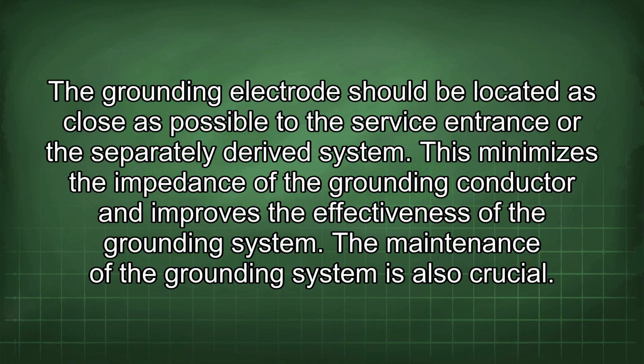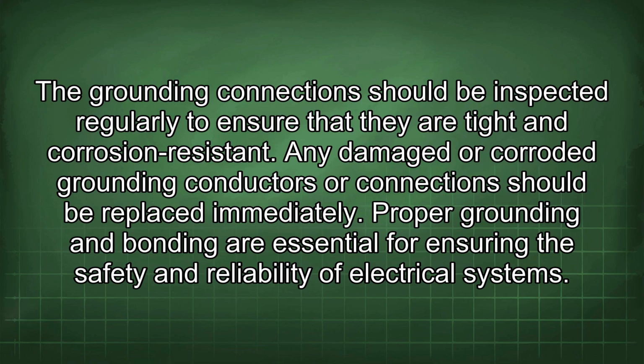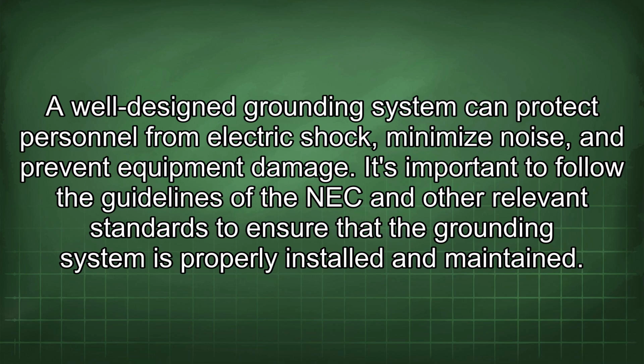The maintenance of the grounding system is also crucial. The grounding connections should be inspected regularly to ensure that they are tight and corrosion resistant. Any damaged or corroded grounding conductors or connections should be replaced immediately. Proper grounding and bonding are essential for ensuring the safety and reliability of electrical systems. A well-designed grounding system can protect personnel from electric shock, minimize noise, and prevent equipment damage. It's important to follow the guidelines of the NEC and other relevant standards to ensure that the grounding system is properly installed and maintained.